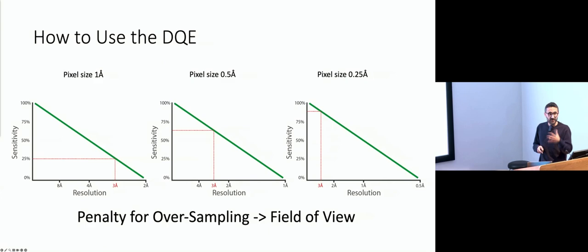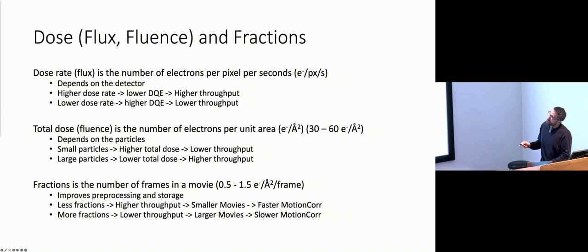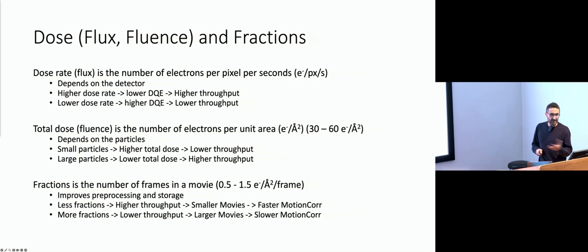When choosing the detector, we also need to consider dose rate, total dose, and fractions. Dose rate is the number of electrons per pixel per second, usually expressed as electrons per second. Higher dose rate gives you lower DQE but much higher throughput — good if your sample is very heterogeneous and needs a lot of data. Lower dose rate gives higher DQE with lower throughput, which is better if you're working with a rock-solid, homogeneous, stable sample.